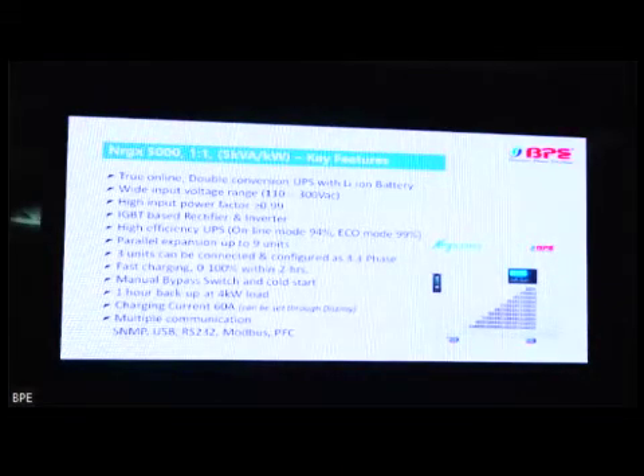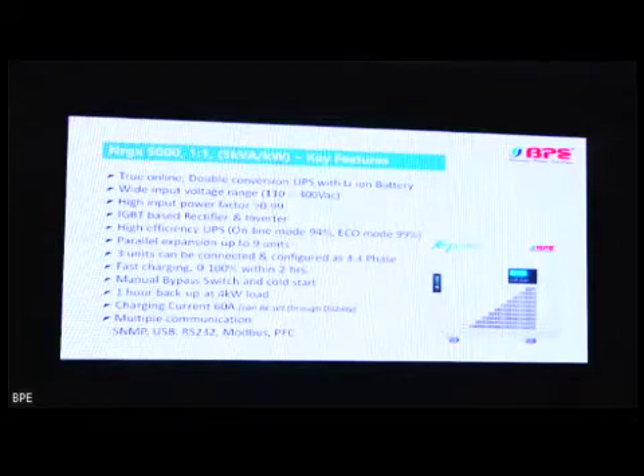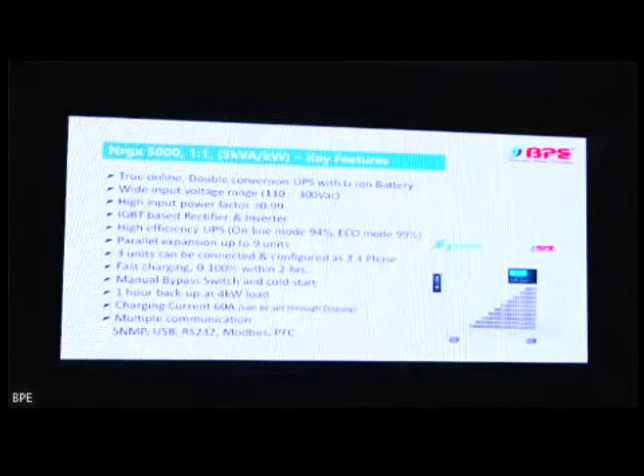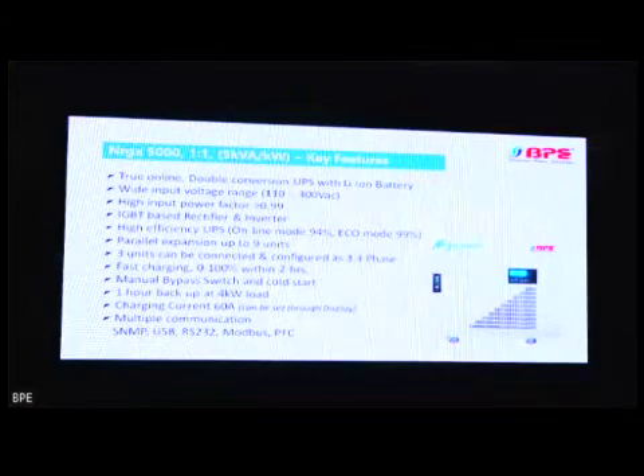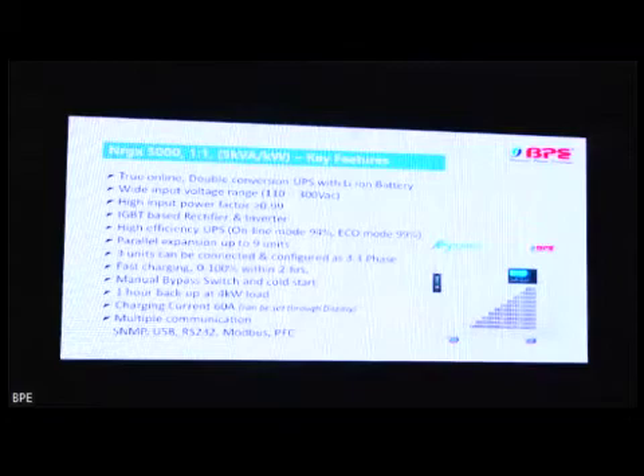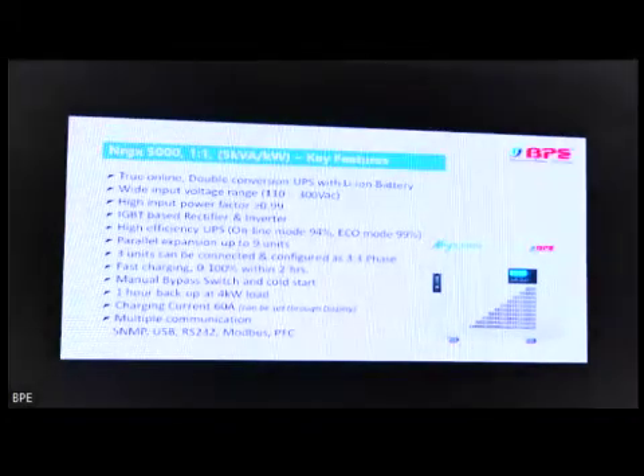And it has got a very high inbuilt charger of 60 ampere. We can configure it from the LCD itself. It's a very big charger suitable for the lithium-ion battery applications, because lithium-ion batteries can be charged with 1C of the rating. So if we are using 60 of lithium-ion battery, so 60 ampere charger is required. And it can charge the battery within 2 hours completely. 1 hour for 70% charging, 2 hours complete charging. With respect to the VRLA batteries, which takes around 8 to 10 hours for complete charging.